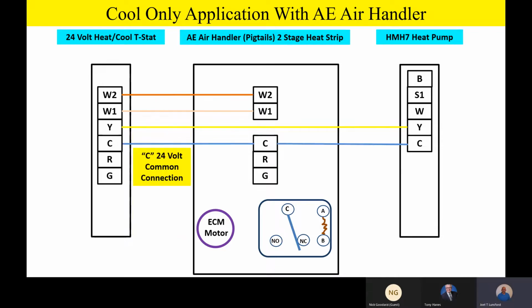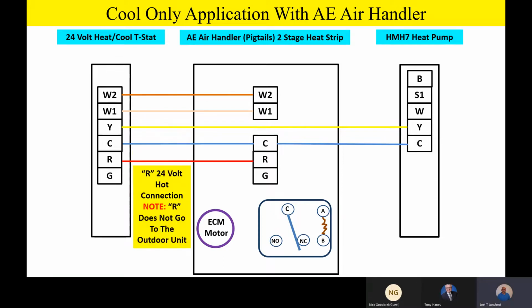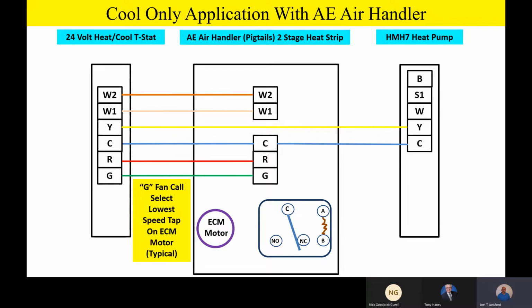And on your 24-volt heat cool thermostat, again, it doesn't have to be a heat pump thermostat. To a good earlier question we had, it doesn't have to be a heat pump thermostat, just a straight cool heat cool thermostat with 2 stages of heat, 1 stage of cool. R will go, again, just to the indoor unit like we had before, and G will be our fan call.